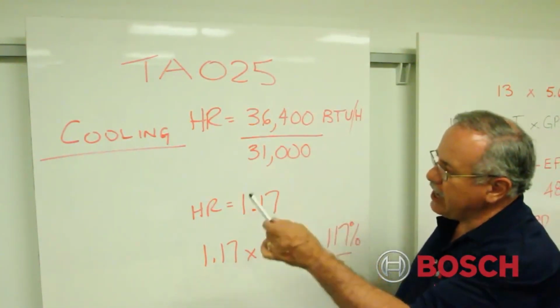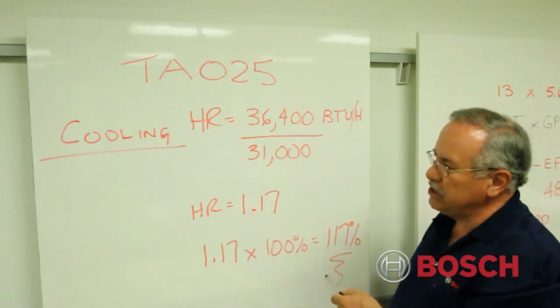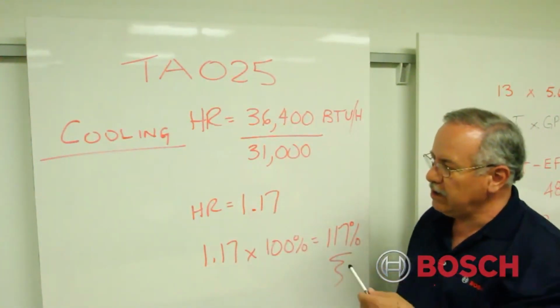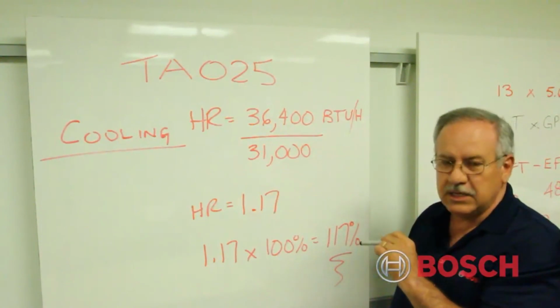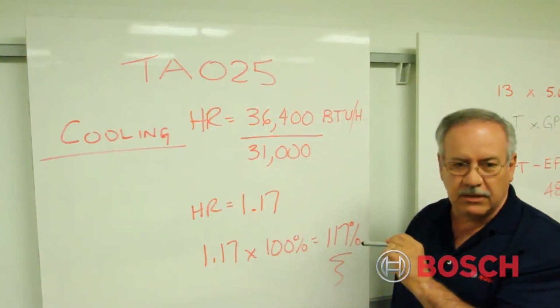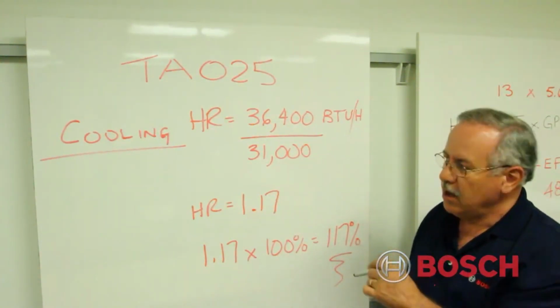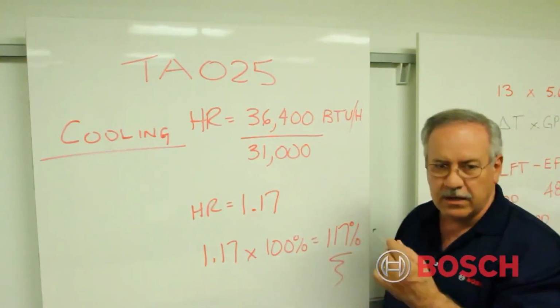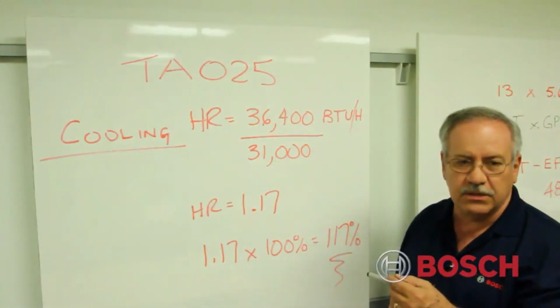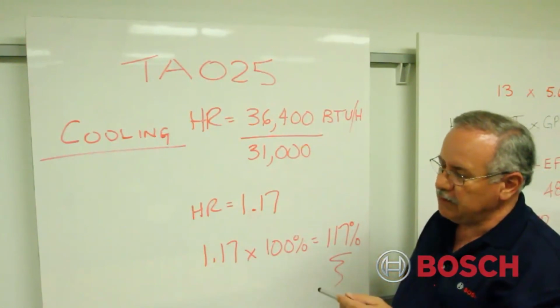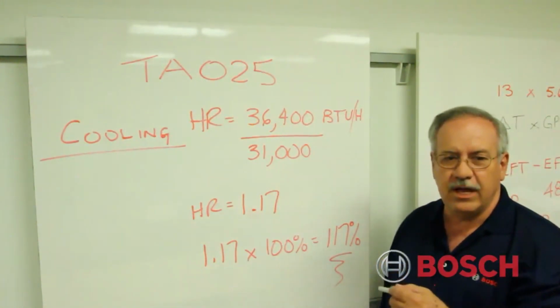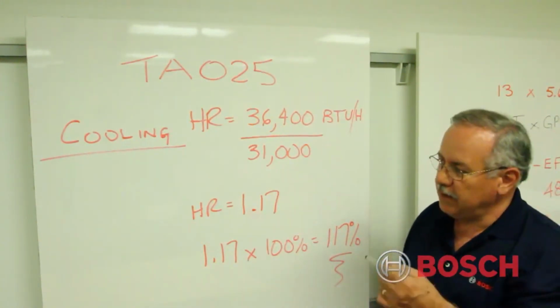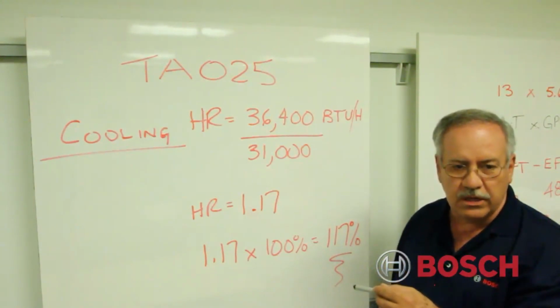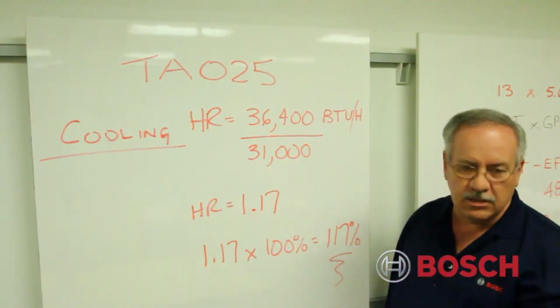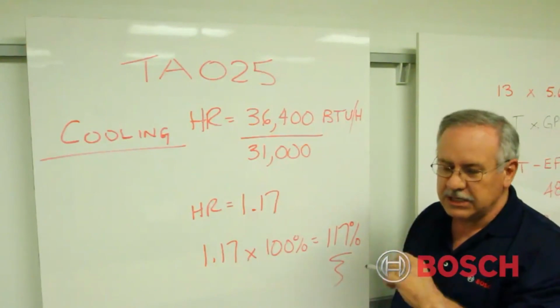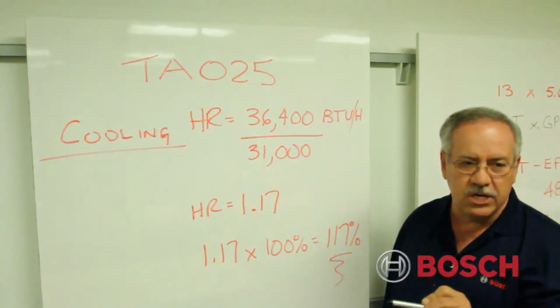So in this particular case, if a technician was in the field and checked it the way we have determined and shown you, this would be acceptable to Bosch and should be acceptable to you as well as the consumer. Whether we're operating in the cooling or heating cycle, the measurements and the calculations are the same. If we were below 90%, then we would have to think beyond the concept that maybe something is wrong with the water circuit or the air circuit or possibly the refrigerant circuit. The last thing we would want to do is put our gauges on this machine.